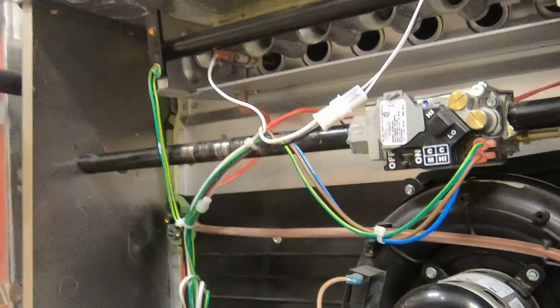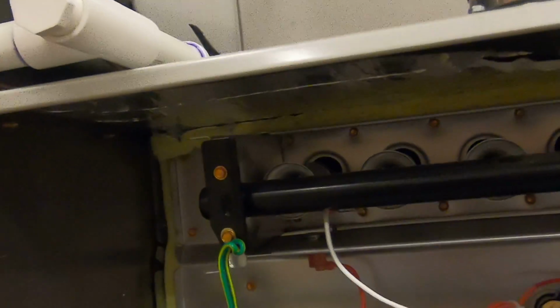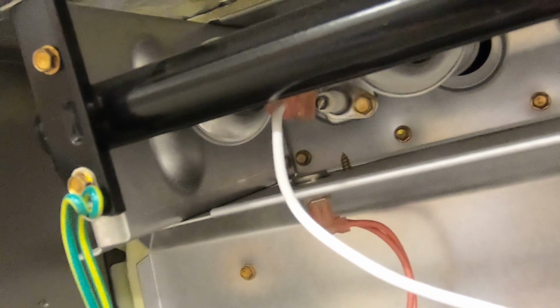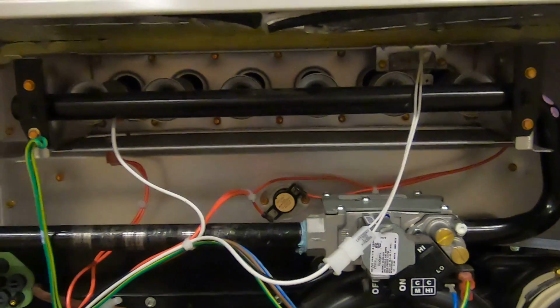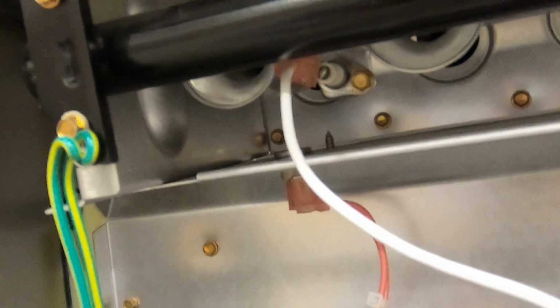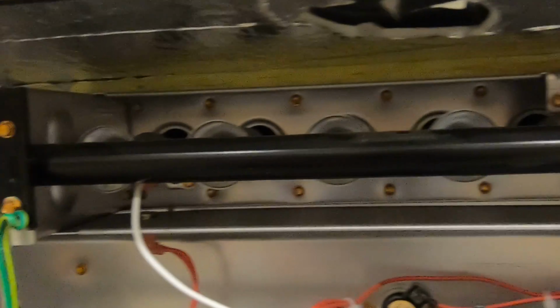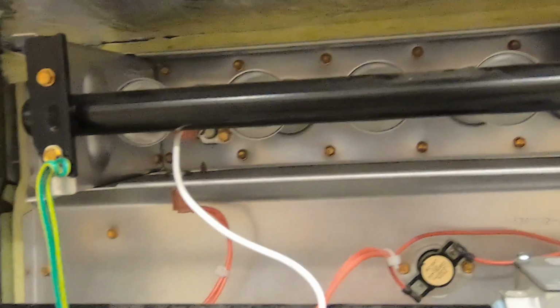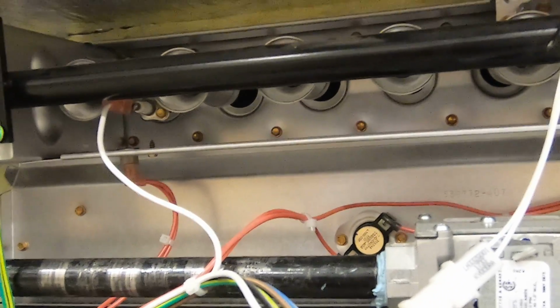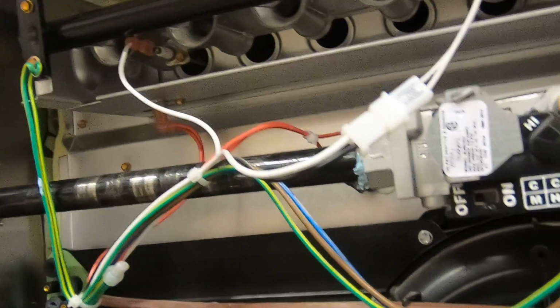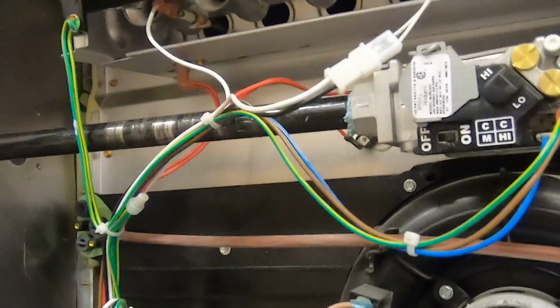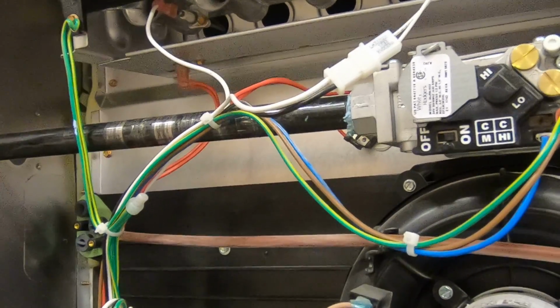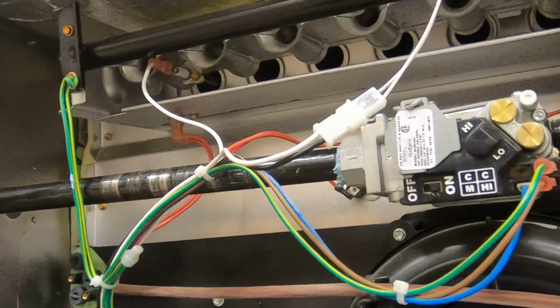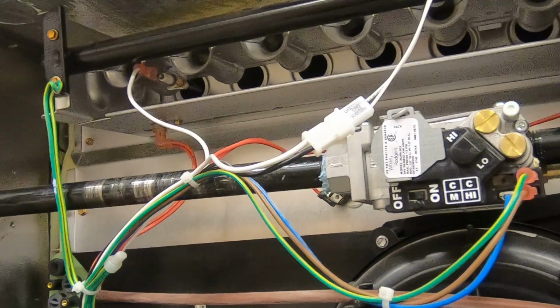sensor is. So if we look at the furnace, that's your sensor underneath. So here's your heater, and then all the way over on the left side underneath is your flame sensor. And that's the sensor that once flame lights from one side, it goes over to the other, and that sensor sends back a small amount of DC microamps telling the board that the flame's lit.